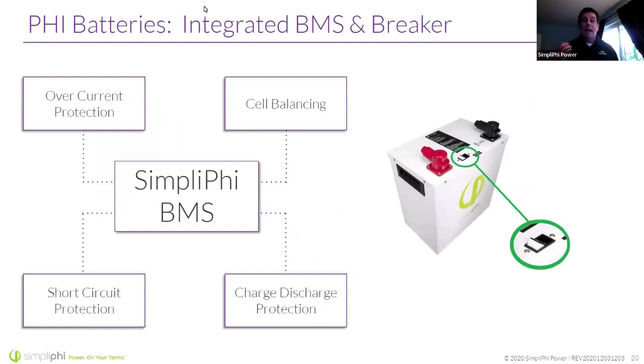All of our SimpliPhi batteries have a BMS system, or battery management system. What does a battery management system do? Well, it can accomplish several things. At the most basic level, our BMS is a form of overcurrent protection—if it sees too much current coming into the battery, it can open the circuit and prevent the cells from seeing too much current. Likewise, it's used to balance the cells during charging. So if we're within an acceptable charging tolerance but some cells are already topped off and others need to catch up, the BMS can distribute that energy. Further, it can offer short circuit protection—if it senses too high a discharge or a potential short circuit, it can open up the BMS.